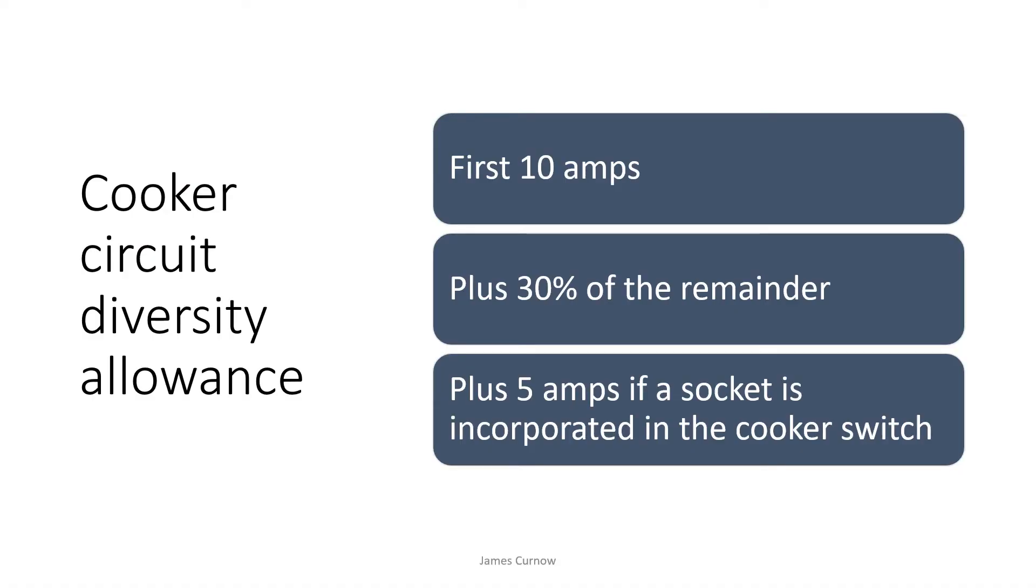The diversity allowance for a cooker in a domestic installation is the first 10 amps plus 30% of the remainder, and plus 5 amps if a socket outlet is incorporated in the cooker switch, according to table A2 in the on-site guide. Please note that allowances are different for business premises or hotels, so please refer to the on-site guide for more information.